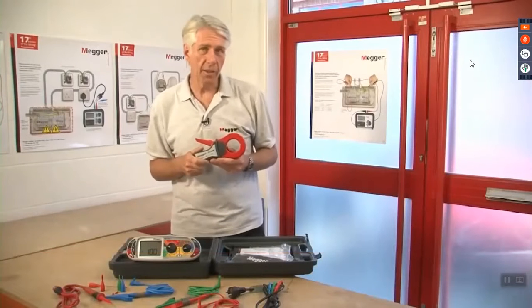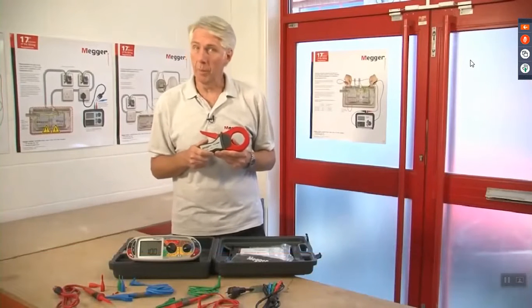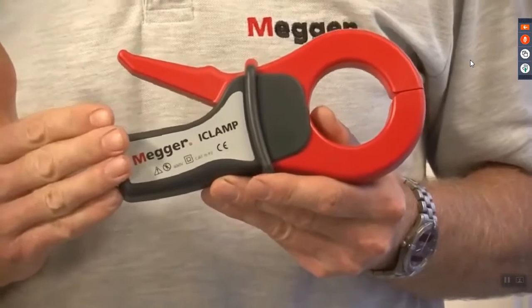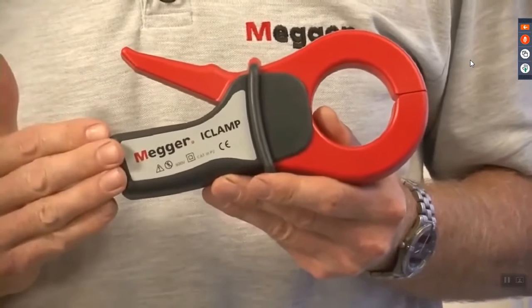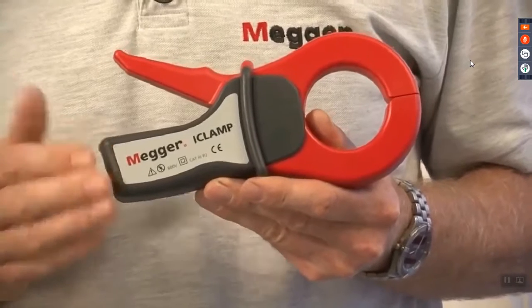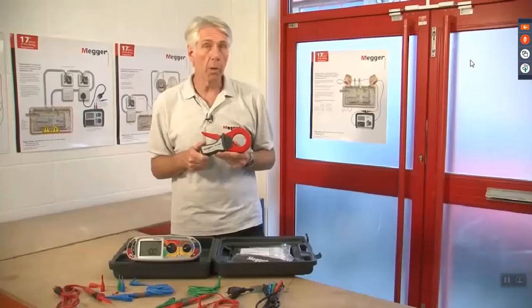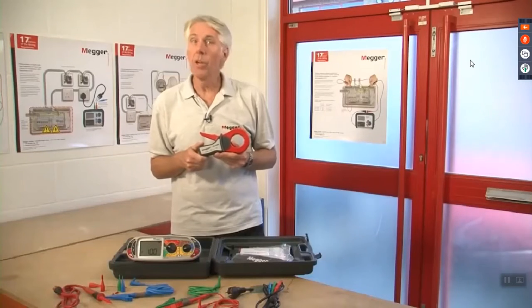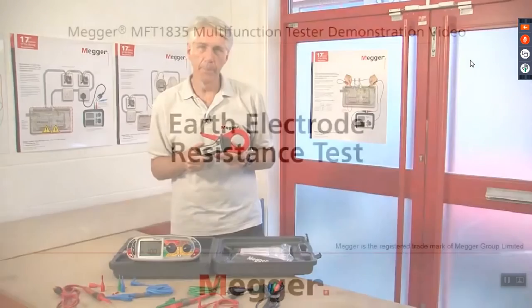The MFT 1835 has the facility of current measurement, so using the optional Megger iClamp, this gives us a range of 0.5 milliamps to 200 amps, and with the resolution down to 0.1 of a milliamp, it can be used for earth leakage measurements.